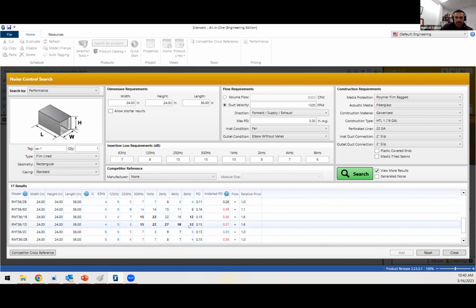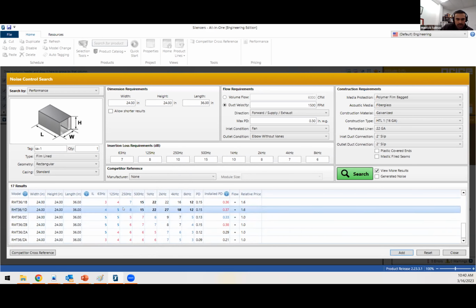Right, so you can see you are short on all of them. This option actually has some blue and a lot of bolded black numbers, which means on all of those you're exceeding performance. Now, the only thing here is that your pressure drop is a bit bigger than the limit that you gave to your system, right? So in that specific case, you might want to allow for more, but there is a quick and easy way to boost performance on the lower octave bands.